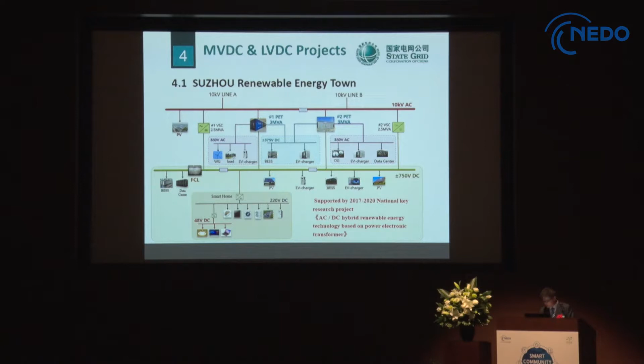And now I'll give the topology about the power electronics transformer. The power electronic transformer uses the modular dual active bridge with high frequency isolation. We have constructed two types of power electronics transformer. One is a silicon IGBT-based power electronics transformer, and the other is a silicon carbide-based PET. We tested the efficiency of these two types of power electronics transformer. For the silicon-based one, the highest efficiency in rated operation is 96.5%.